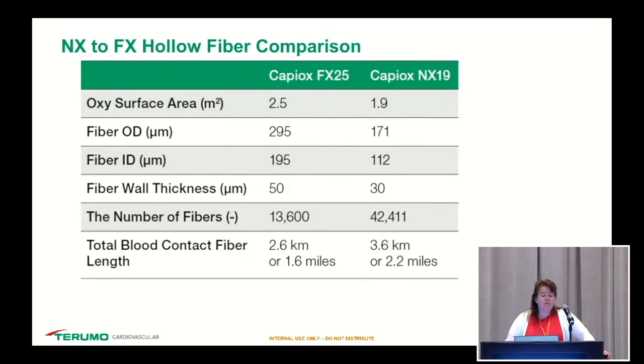So this is the NX next to the FX hollow fiber comparison. The surface area of the FX25 is 2.5, whereas the CAPIOX NX19 is 1.9. Sorry, the outer diameter is 295 and it's 171. Basically, at the bottom, you can see that the number of fibers for the NX19 is 42,000 fibers compared to the 13,000 that the FX has. If you were to take those fibers and go end to end, the NX19 would have 2.2 miles of fibers. So as you can see, it decreases the shunt fraction, and it allows us to ensure that the blood will be oxygenated as it goes into that oxygenator and out.